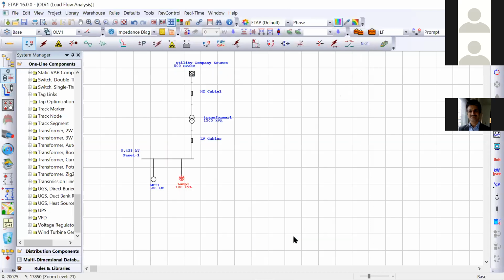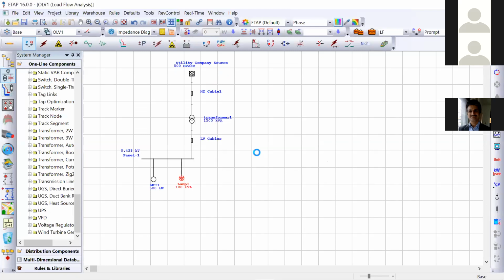Presently we are going with the basic, default data to perform this load flow. Now our network and our network load flow configuration is ready. So we will simply perform the load flow calculation on this network. It has now performed the load flow calculation. The load flow is converged.